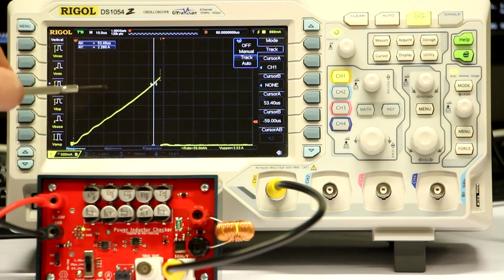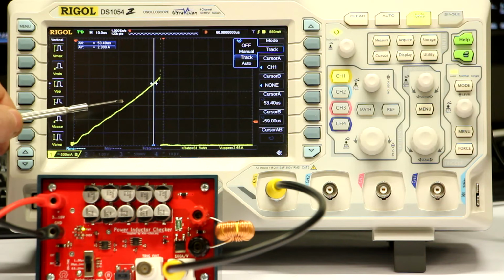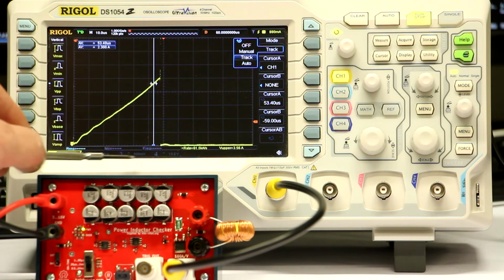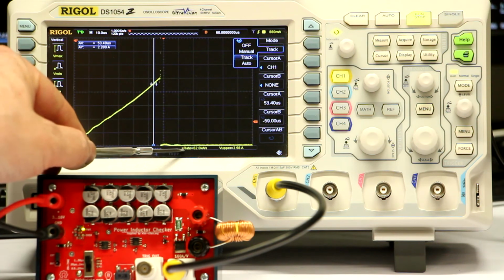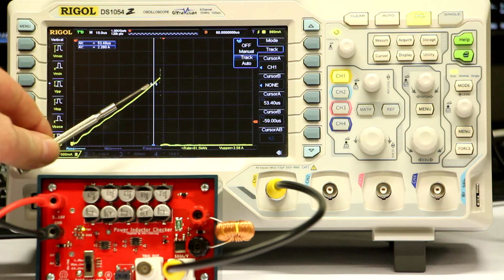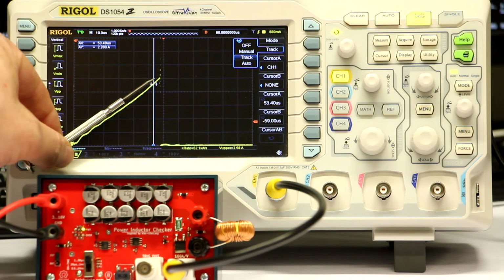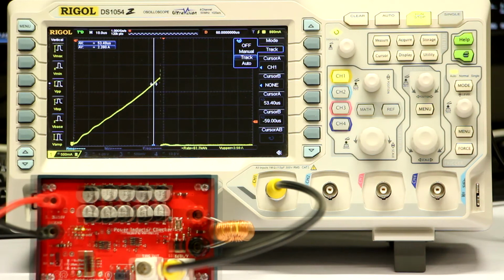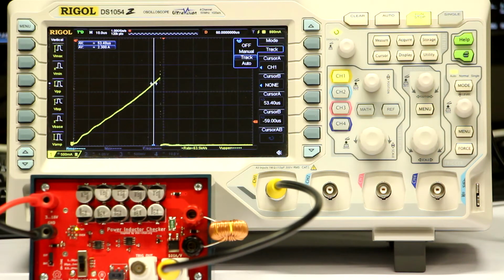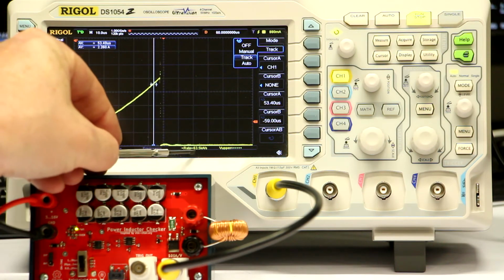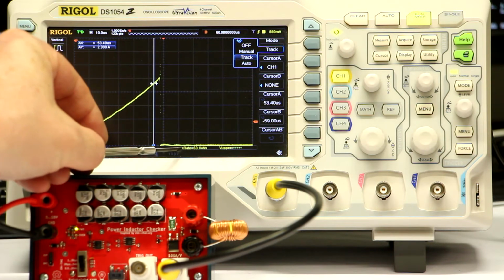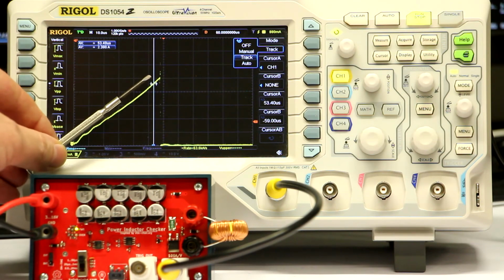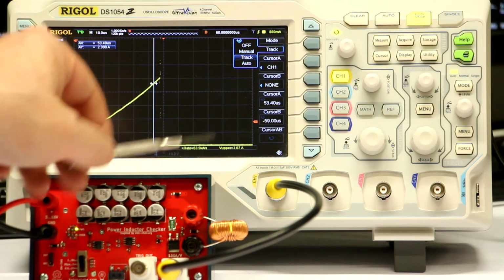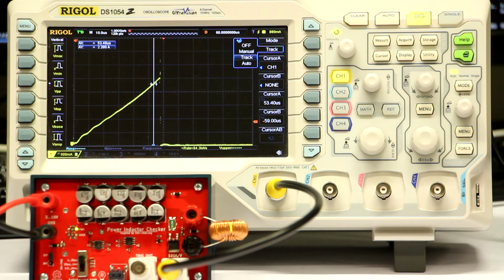Now we could go with this value already into our formula, but there is still an easier way. Here on the measurement values, you can set the rate of, which is nothing else but the slope of our linear graph here. So the only thing we now have to do is we have to divide our supply voltage by the rise rate, the slope of our curve, which is given as, jumping around a bit, 63 kiloamps per second.